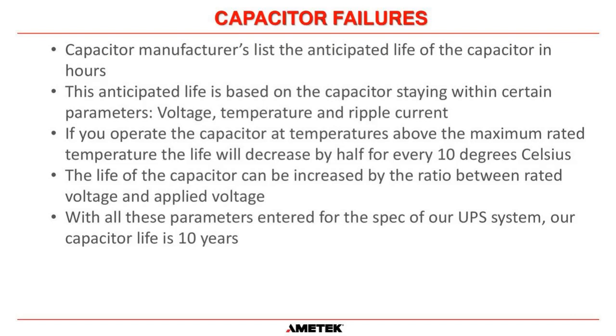Okay. So if you operate the capacitor at temperatures above the maximum rated temperature given by the manufacturer. So let's just say, for example, they say that 50 degrees Celsius is the highest temperature that they want that capacitor operated at to give you its calculated lifespan. Then the life of that capacitor will decrease by half for every 10 degrees Celsius above what it says on the data sheet. So in that circumstance that I just told you, the 50 degrees capacitor, if the temperature of the system went up to 60 degrees, that capacitor's lifespan has been halved.